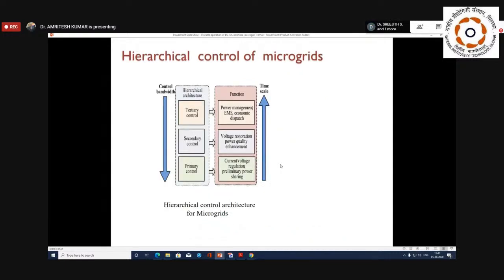So if you see the control part, basically this microgrid control is divided into three parts. One is primary control, secondary control, and tertiary control. So primary control means that we are talking about the converter level control. Basically, this is primarily being used for current and voltage regulation via power electronics interface. But whatever the demerits, we'll see in the course of the slides, that we are going to face some issues with the primary control. So that's why we have to go for a higher level control, that is called secondary control. Basically, secondary control and primary control we can say are independent, but they have to work together. And that too, this control is going to be governed only through the power electronics converter.